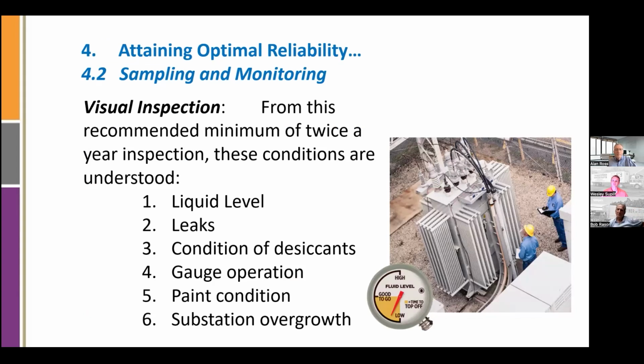These are the things you pick up on a visual inspection. We recommend at least once a year, but twice a year better. You want to look for level leaks, the condition of your desiccant. Free breathing transformers are becoming more and more rare as the aging process continues, and the oil preservation systems are different. Not so many free breathers. The condition of your gauge, the level gauge in particular, you want to make sure it's reading accurate. That's a combination of looking at temperature and the level, just to make sure it's at the right place so the transformer doesn't overheat.